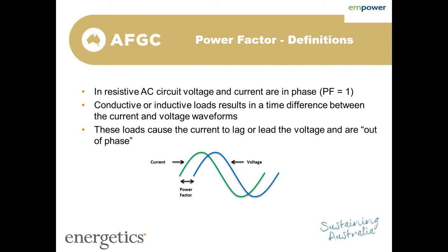We get issues arising when we have capacitive or inductive loads on site. The main loads we see are inductive loads — motors are the most common — but there's a range of others. Some, like fluorescent lights, are actually slightly capacitive. What these loads do is result in a time difference between the current and voltage waveforms. We refer to this as the current lagging or leading the voltage. When there are capacitive or inductive loads and the Power Factor is less than one, the voltage and current are said to be out of phase. The more they are out of phase, the lower the Power Factor.